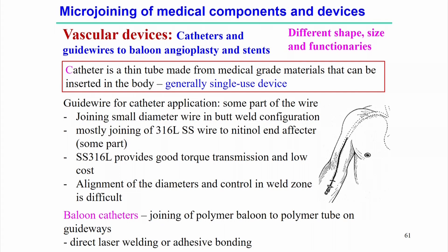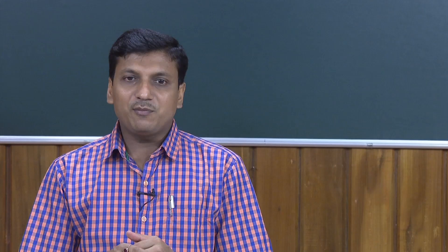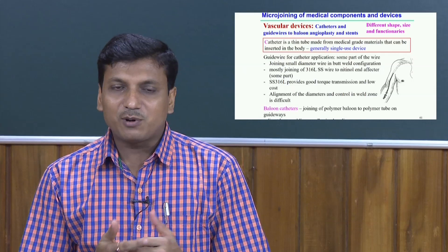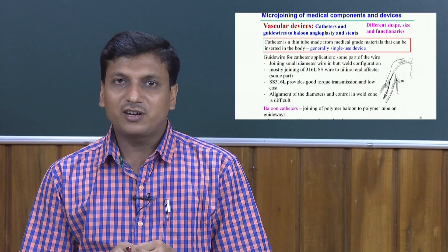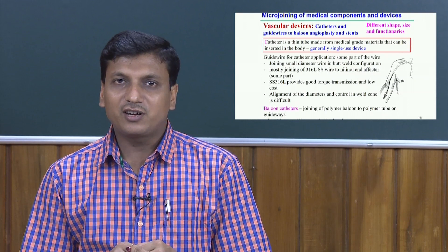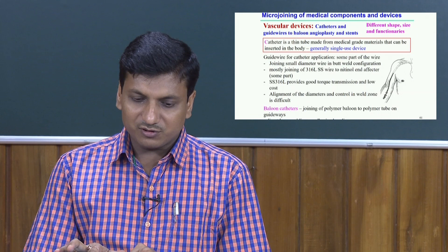SS316L stainless steel is used because it provides good transmission and low cost, but alignment of the diameter and control in the weld zone is really very difficult. In this case, laser welding can be a good solution. For balloon catheters, joining of the polymer balloon to the polymer tube on the guide wires is sometimes required, and in this case either direct laser welding or adhesive bonding is generally used. These vascular devices are generally single-use.